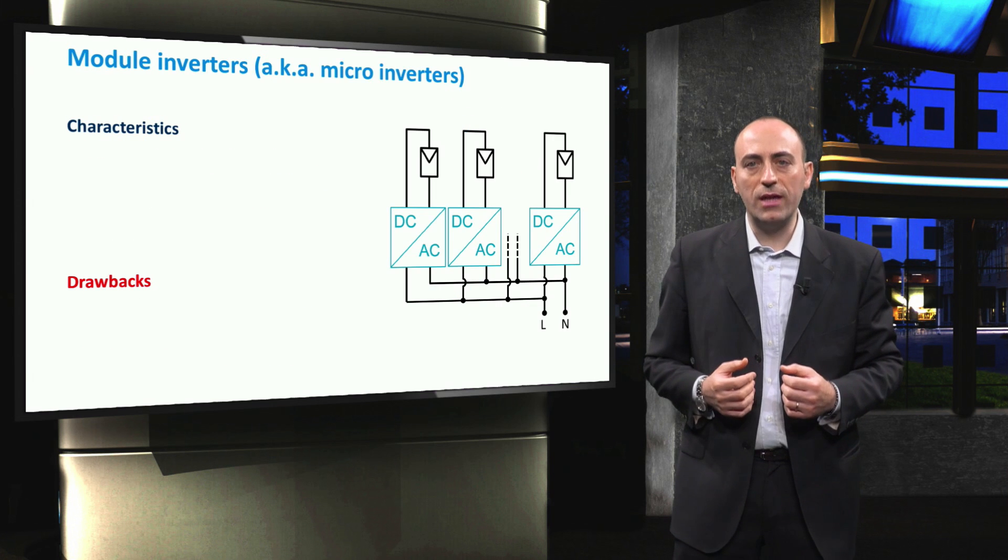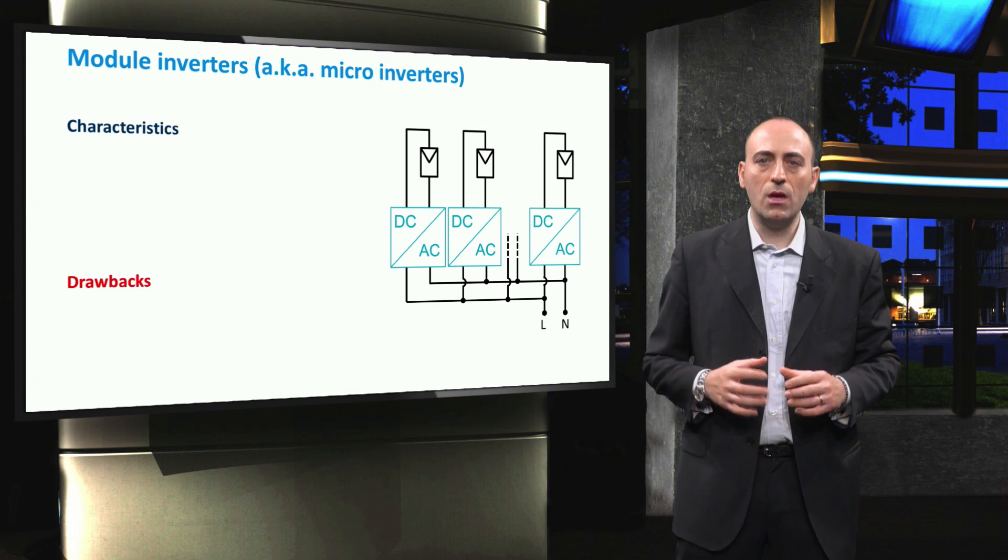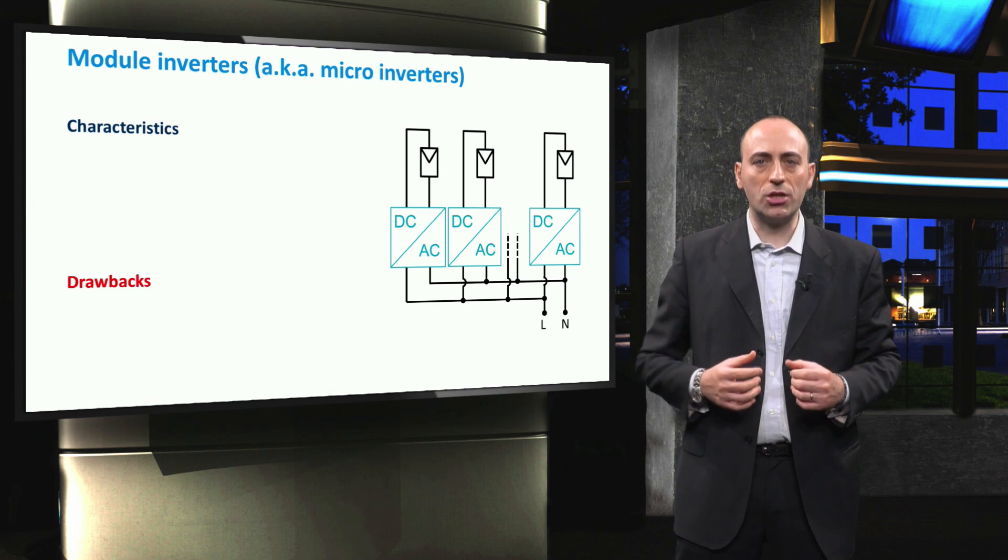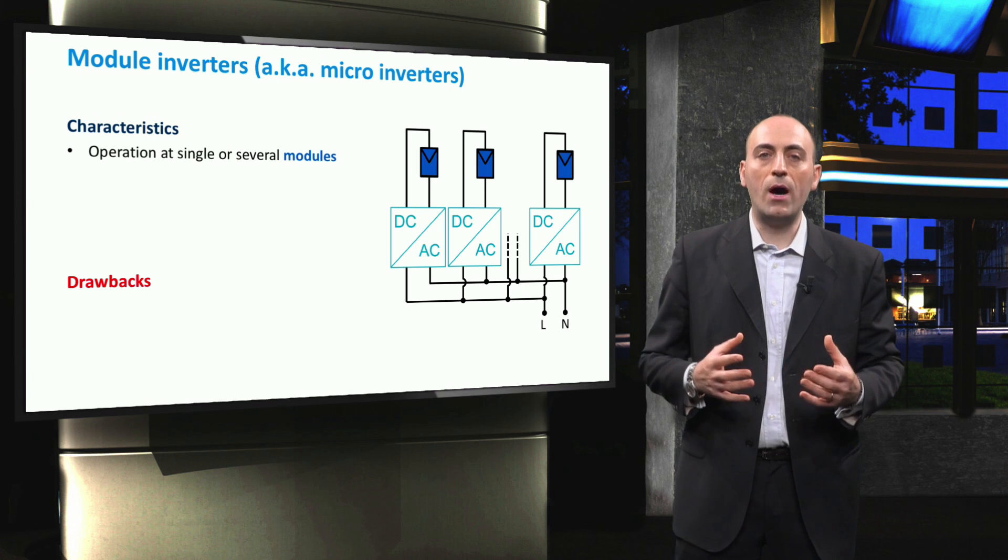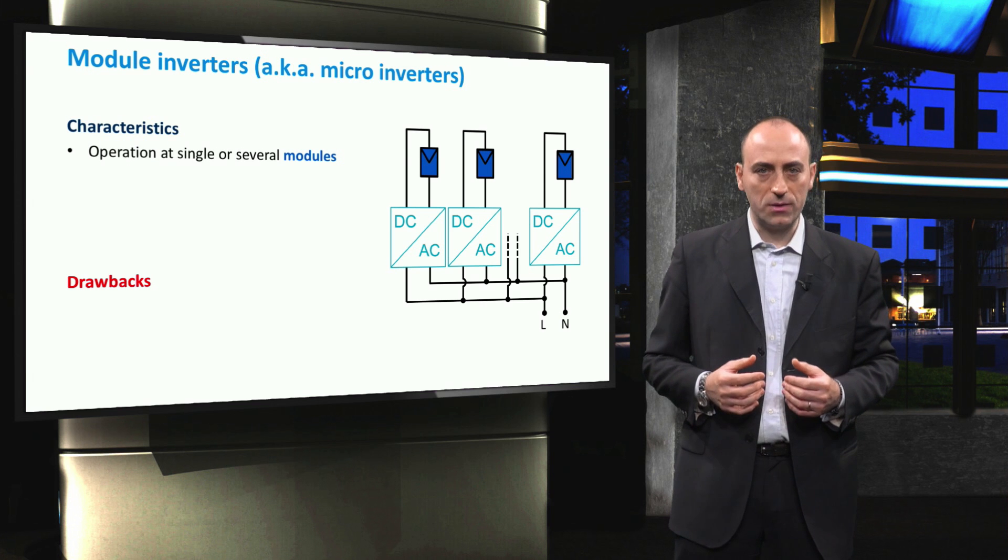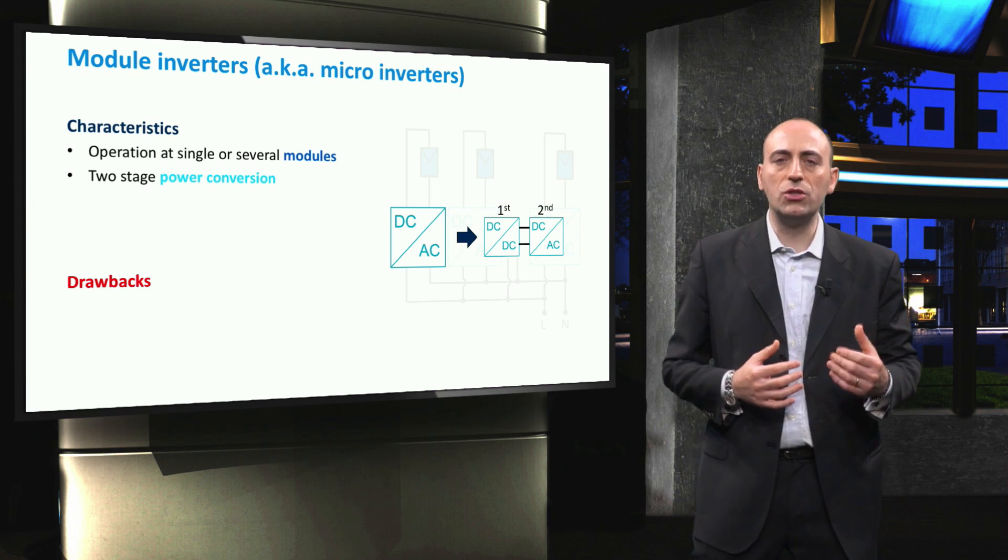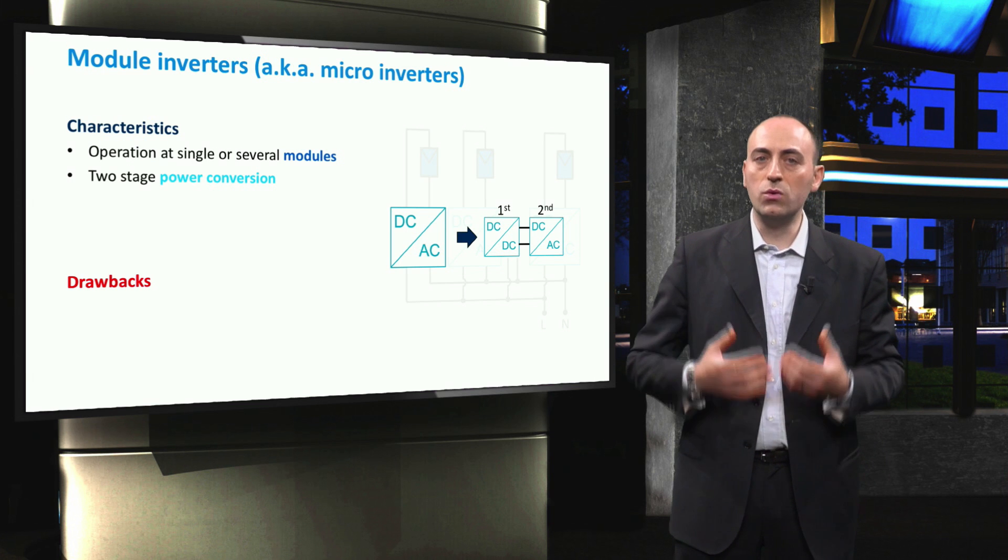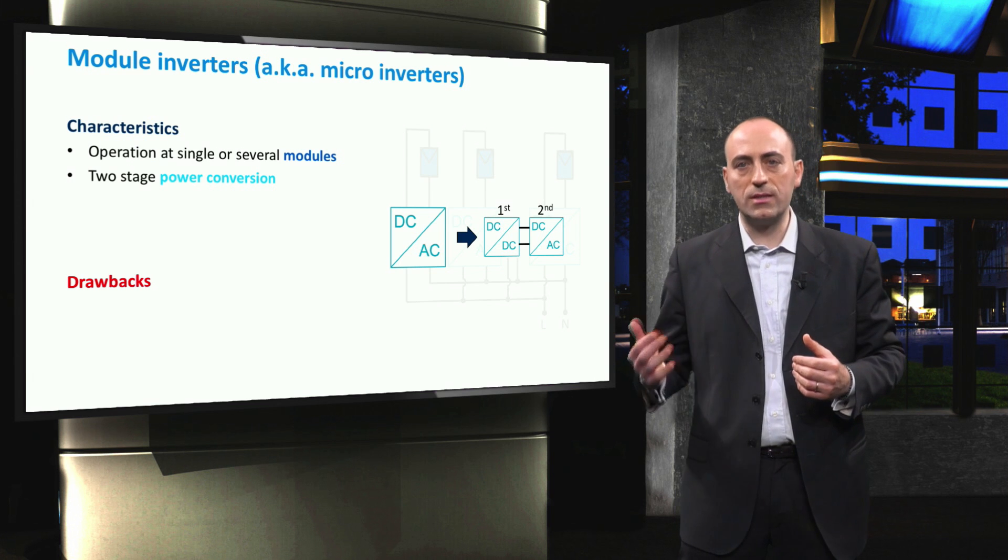A very different architecture is that of the module inverters, also called the micro-inverters, because they are just as big as the junction box. These inverters operate directly on one or several PV modules, and have power ratings of several hundreds of watts. Because of the low voltage rating of the PV module, these inverters often require a two-stage power conversion. So, in the first stage, the DC voltage is boosted to the required value, and then it is inverted to AC in a second stage.